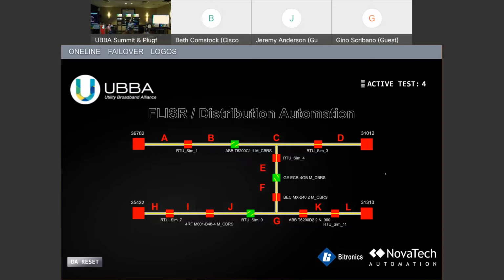The key thing that we're getting now is sometimes distance to fault information. And that's really challenging in a branched distribution network, because just because I know the distance to the fault doesn't mean I know where it is, because there's a lot of different pathways. But when you get that lockout, then the automation scheme kicks in.